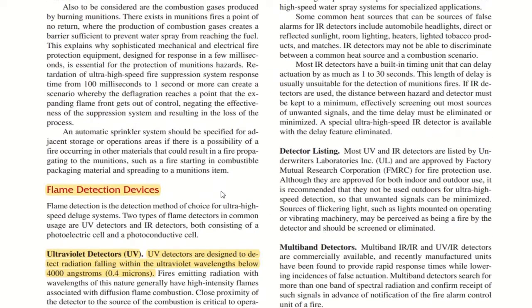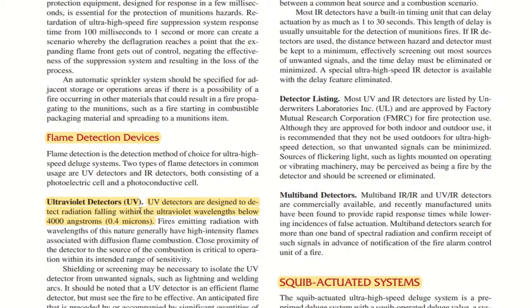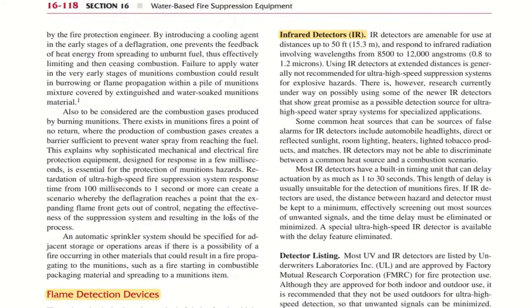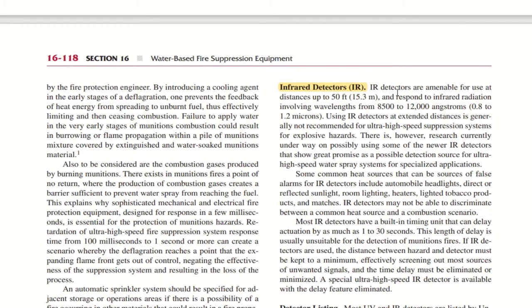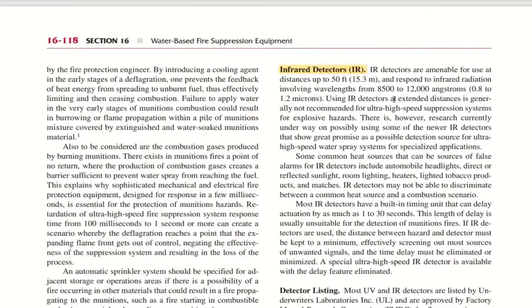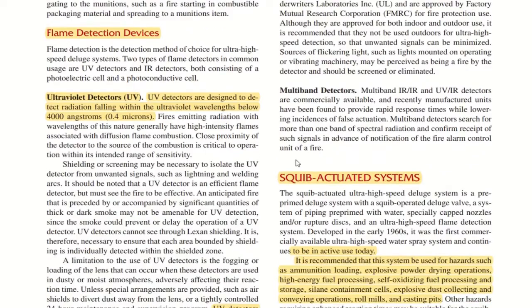Here you have flame detection devices, ultraviolet detectors. This is a very important topic which you need to go through. UV detectors are designed to detect radiation falling within the ultraviolet wavelengths below 4000 angstroms, 0.4 microns. For infrared detectors, they have given some data, so you just go through this.